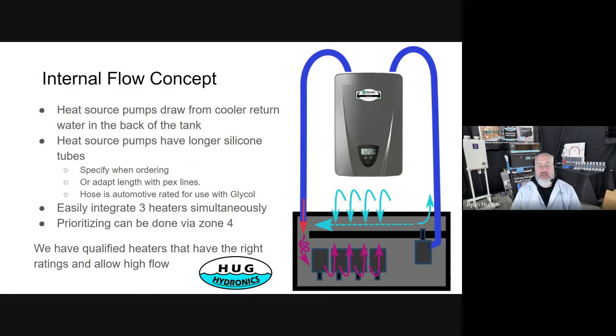Inside, the flow is just a little more subtle. The return water comes into this baffle in the back. There's a particular section where all the cooler return water comes in. Then the pump in the corner draws that coldest water and sends it up to the water heaters, and then returns it. It mixes with the return flow and warms all the water to a higher temperature, and then these pumps send it back out to the floor.